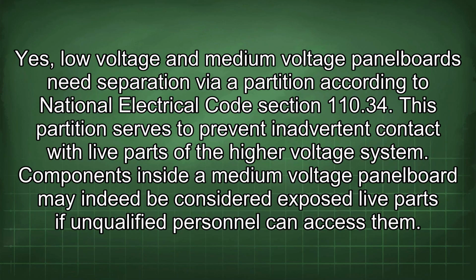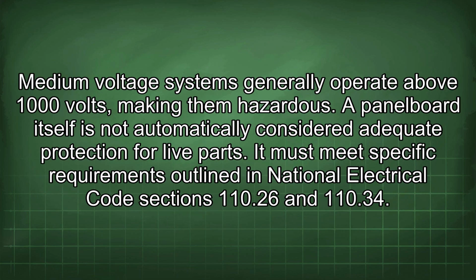Yes, low voltage and medium voltage panel boards need separation via a partition according to National Electrical Code Section 110.34. This partition serves to prevent inadvertent contact with live parts of the higher voltage system. Components inside a medium voltage panel board may indeed be considered exposed live parts if unqualified personnel can access them. Medium voltage systems generally operate above 1000 volts, making them hazardous.